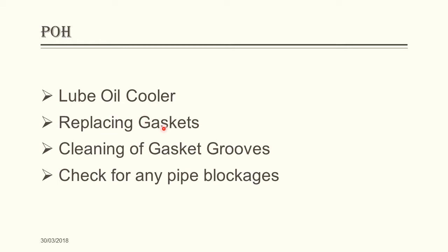Coming to the replacing of gaskets: when a gasket requires replacement, following steps are to be followed for removing the gasket from the plate. Remove the plate from the frame and lay it on a clean flat horizontal surface. Examine and note exactly how the gasket is positioned, particularly what grooves the gasket does and does not occupy. By inserting a screwdriver, take up the gasket and by pulling it slowly, remove the whole gasket. Take care not to scratch the plates with a tool. If the gasket is not removed easily, then immerse the plate assemblies in a 10–15% caustic bath solution at 140–180°F for approximately 8 hours. The caustic will soften the glue and the gaskets can be removed easily.